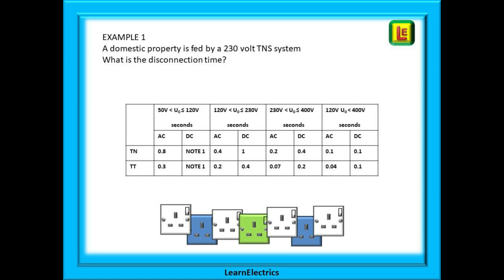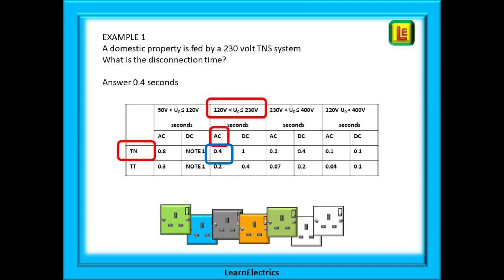Let us use the table to work out a few examples, starting with example 1. A domestic property is fed by a 230 volt TNS system — what is the disconnection time? Looking at the table we find the row TN for TNS on the left. At the top, choose the voltage range 120 to 230 since our nominal voltage does not exceed 230 volts. It is AC, so choose the correct column. Where the column and row meet is the answer — here in blue, it is 0.4 seconds.